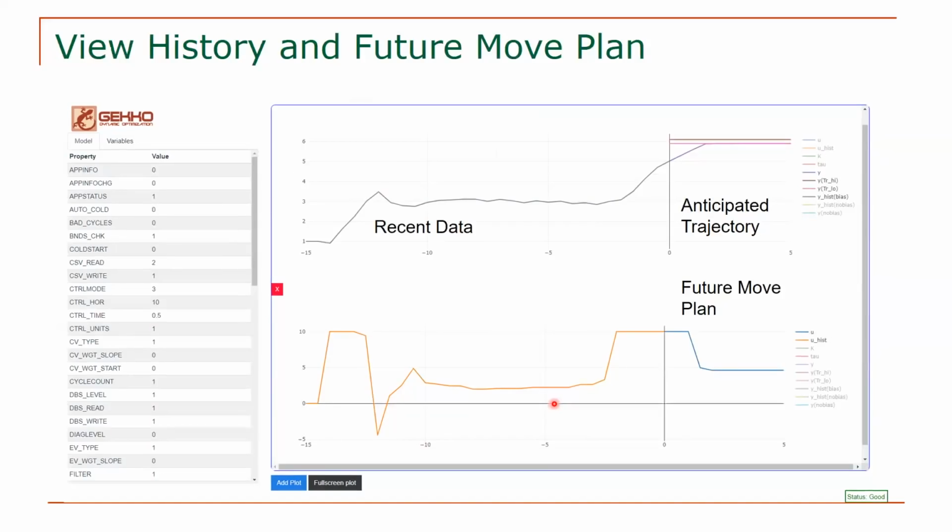Also, here's that closed loop online with the first order models. When you solve it in a loop, it stores some of your recent data. Here's the controlled variable, here's the manipulated variable, here's what has happened, here's our expected moves of the manipulated variable and the anticipated trajectory for the controlled variable. You can see that it expects with this move, it should fall within the set point band. Just stop that one during that transition to a new set point. So this is kind of what we imagine engineers could use to watch their model predictive control online.